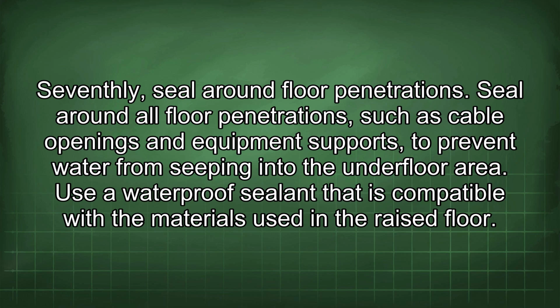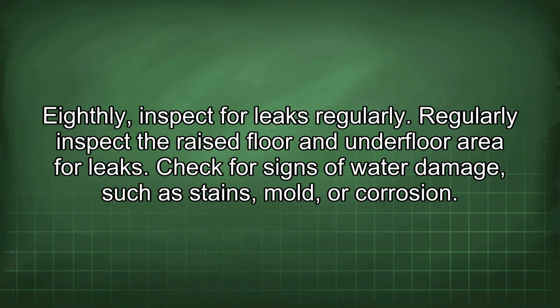Seventhly, seal around floor penetrations. Seal around all floor penetrations, such as cable openings and equipment supports, to prevent water from seeping into the underfloor area. Use a waterproof sealant that is compatible with the materials used in a raised floor. Eighthly, inspect for leaks regularly. Regularly inspect the raised floor and underfloor area for leaks. Check for signs of water damage, such as stains, mold, or corrosion.